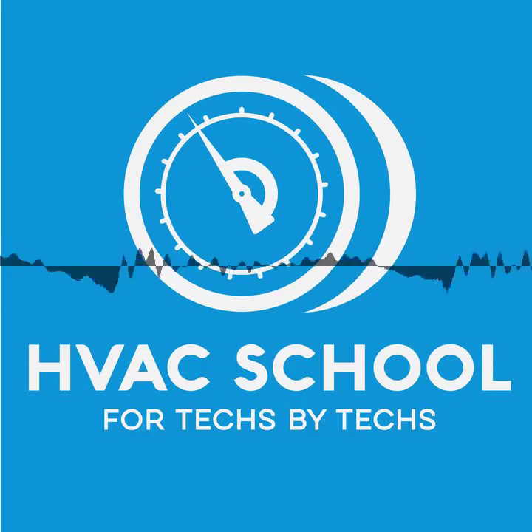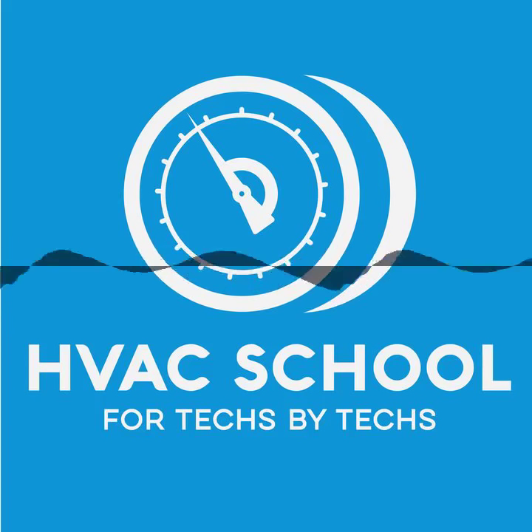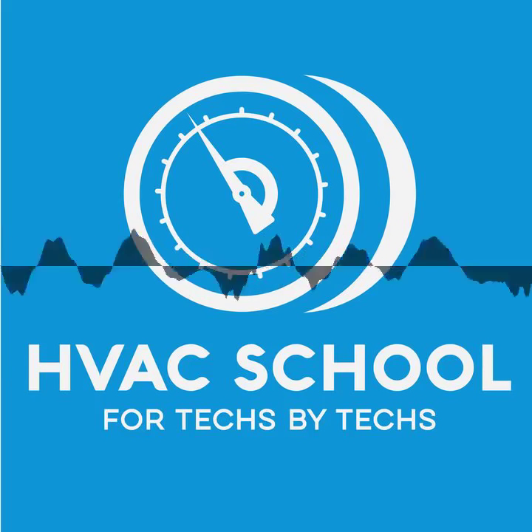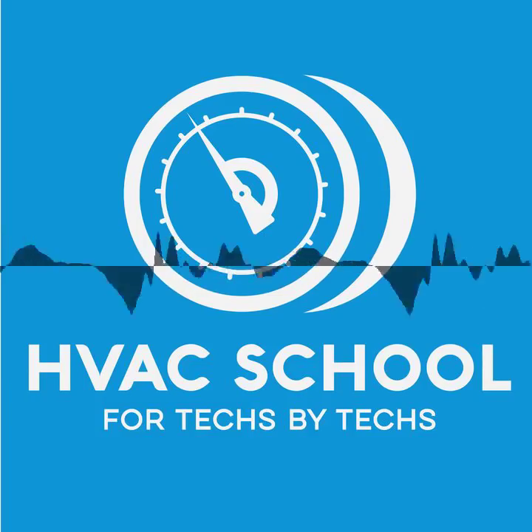Yeah, a couple things when it comes to leakage. Pressure test, obviously. Visually inspect anything that you're connecting, making sure that it looks good. Bubble test all of your joints while under pressure. And then when you get to vacuum, make sure that you pull a very deep vacuum below 500 microns, and then make sure that it will hold for the prescribed period of time in that decay test that we talk about so much on this podcast, which again goes into the vacuum side of things. So make sure that you pay attention to all those things.